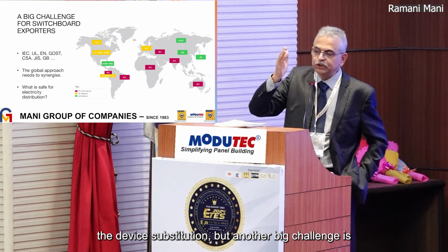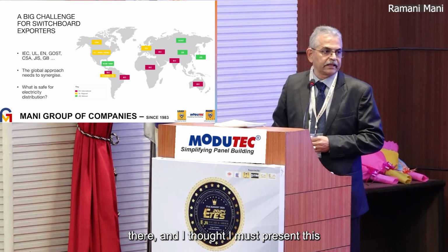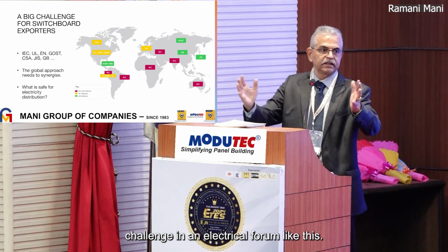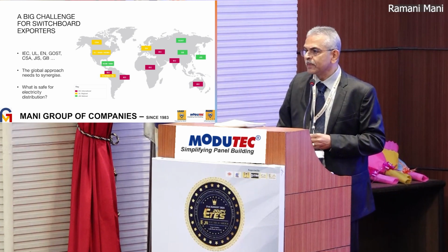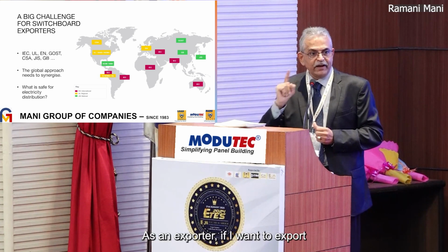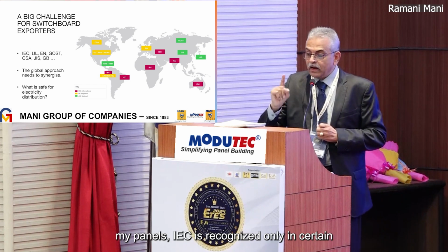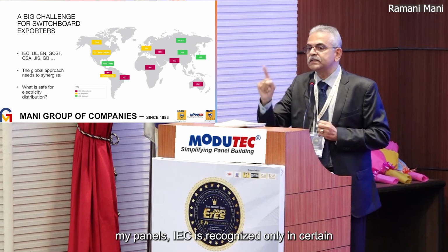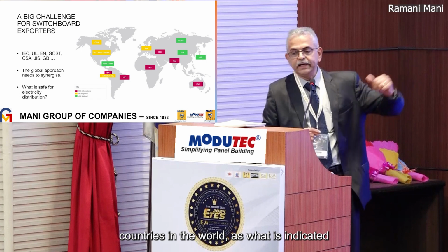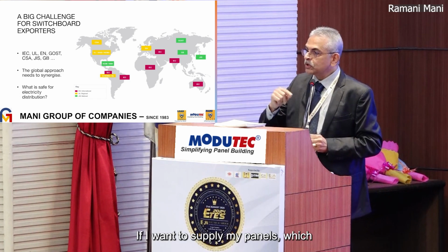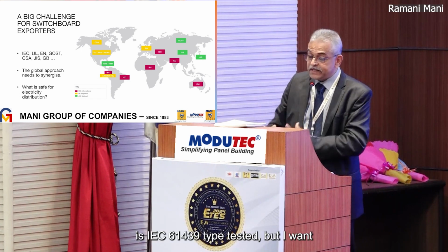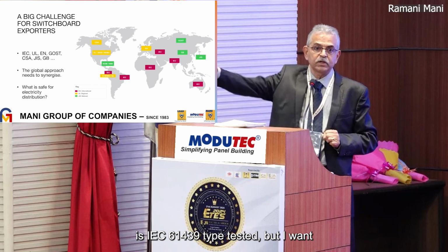Now, the big challenge - one is the device substitution, but another big challenge is there, and I thought I must present this challenge in an electrical forum like this. As an exporter, if I want to export my panels, IEC is recognized only in certain countries in the world, as indicated here. If I want to supply my panels, which is IEC 61439 type tested, but I want to supply it to America, Americans say, no, you have to get it type tested as per UL standards.